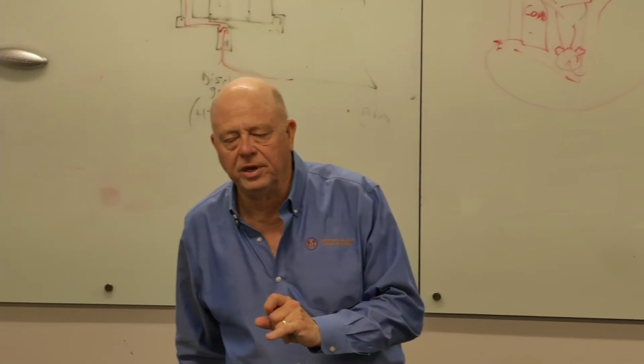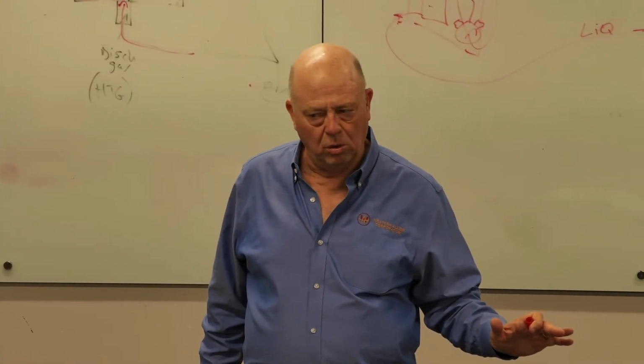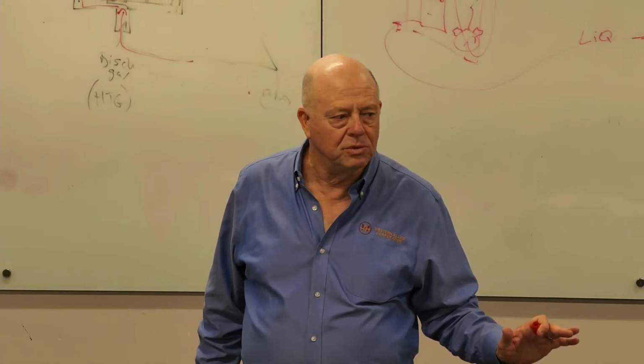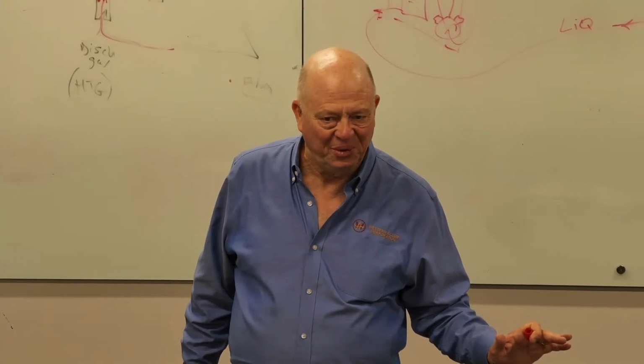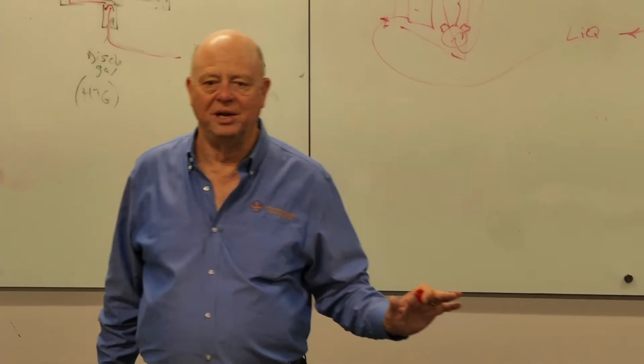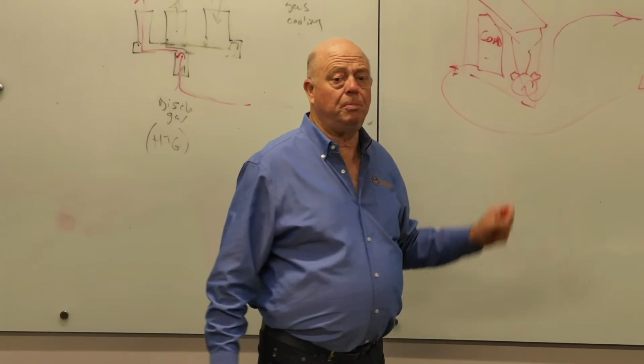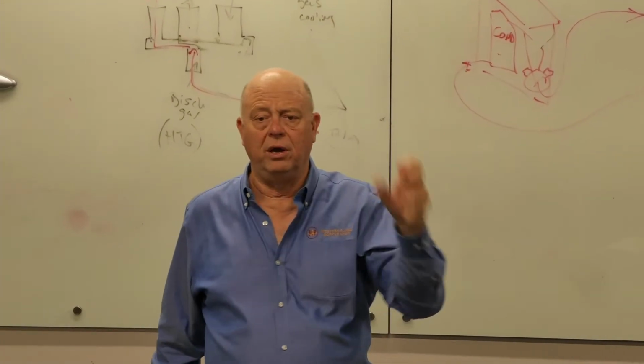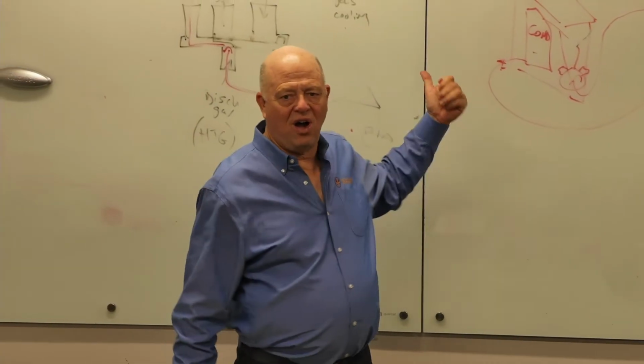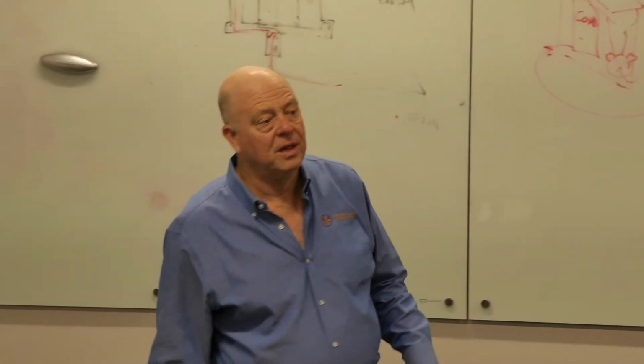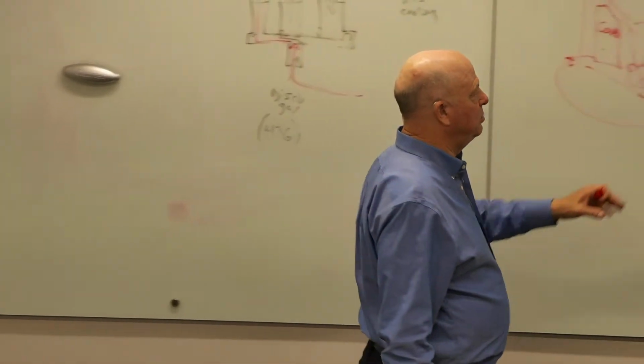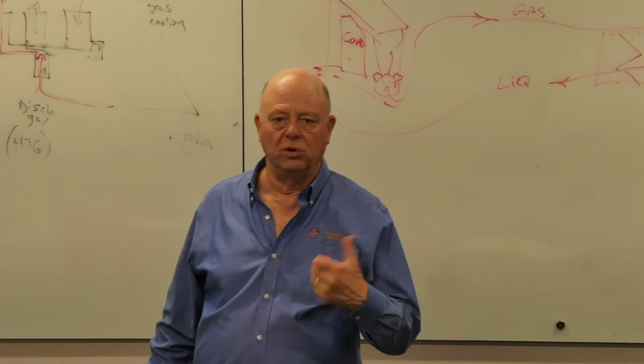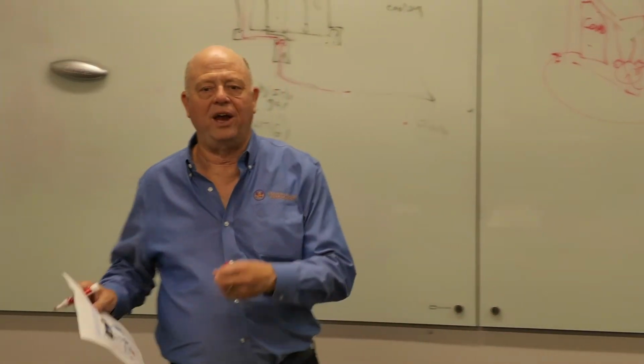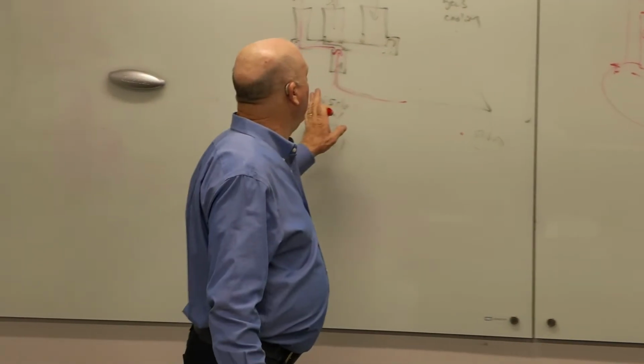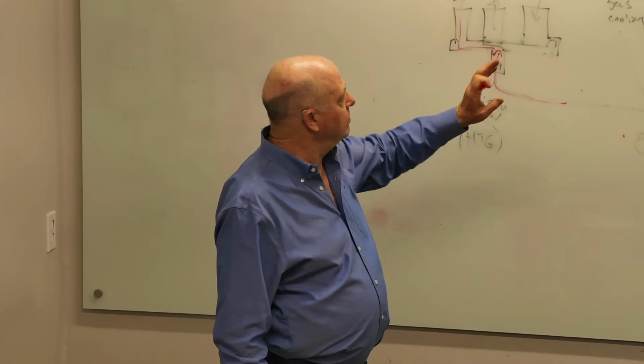So one thing to remember for a heat pump is that when it's in the heating mode, it is not always blowing hot air. Sometimes it's blowing cold air. You can get kind of funny drafts sometimes, okay? They have super duper ones that just circulate gas and don't blow air, but those take longer to thaw out the thing outside because they don't have the load that they're putting on this thing. Okay? VRF, as a side note, gets around some of that because you probably have a bunch of fan coils on one condensing unit and they all don't defrost at once. You can kind of stagger what you're doing a little bit more. Okay, so defrost mode.